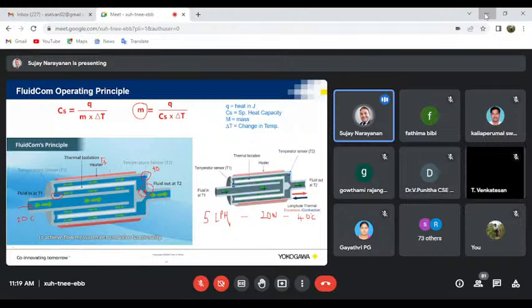But since we are in case of FluidCom, since it's only one device, then we are able to get rid of all these things, and we can daisy chain and we can do the wireless communication as well. Okay. But here you need separate logic solvers and everything in your DCS programming, function blocks, routine has to be defined, but here you need not do that because everything is happening in the field. Yeah. So that's one thing. Okay, I'll skip this. Not important. Yeah, this is what is important.